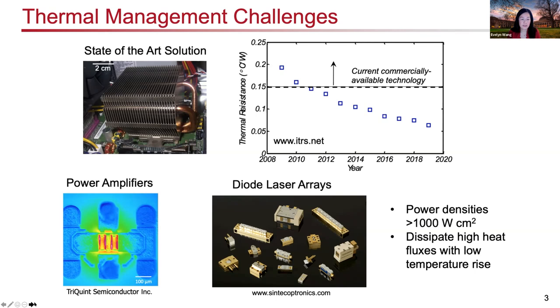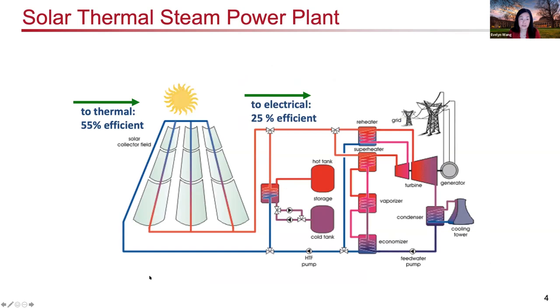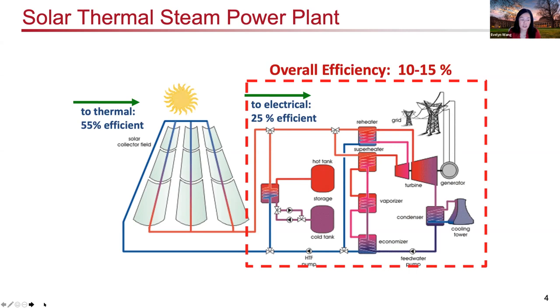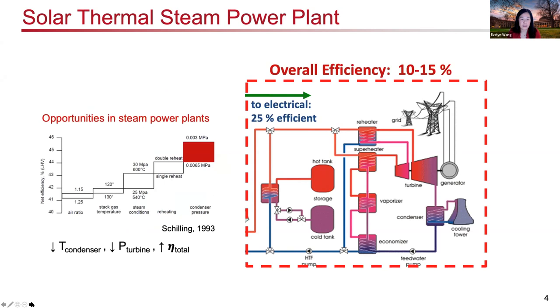Thinking about larger-scale systems such as a solar thermal steam power plant — these steam power plants still have very low overall efficiencies of about 10 to 15 percent. A significant aspect of that is the power cycle itself, where thermal to electrical conversion efficiency is only about 25 percent. This relies on phase change — the evaporation and condensation of water. If we can enhance the condensation processes to decrease the temperature of the condenser, we can decrease the turbine back pressure and potentially increase cycle efficiency significantly.